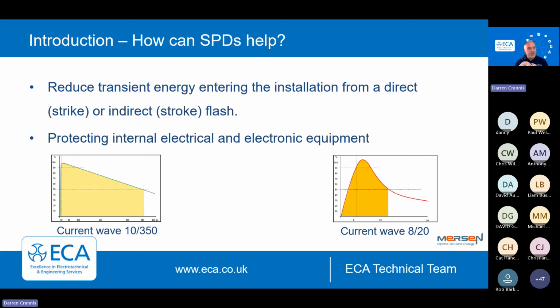And that's why we have mentions of Type 1 protection, zone LPZ 1, in our standard, because we need to implement that. But importantly, when you get a lightning strike, it gets to 90% of its energy within 10 microseconds. It's dead quick. And it takes 350 microseconds for that energy to deplete to 50%. It's a large amount of energy. When you come to indirect, so our lightning strikes or switching, it's a very, very small magnitude. It's up to magnitude much quicker, 8 microseconds, and it's down to 50% within 20.